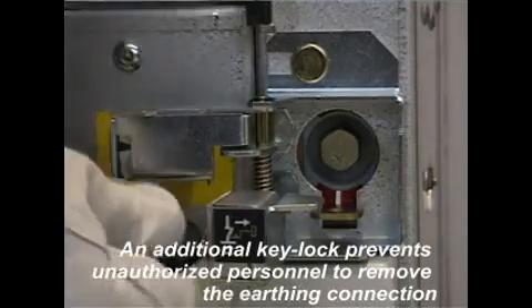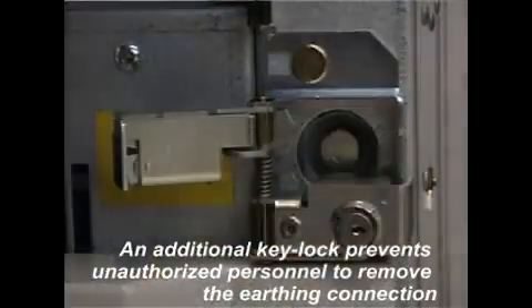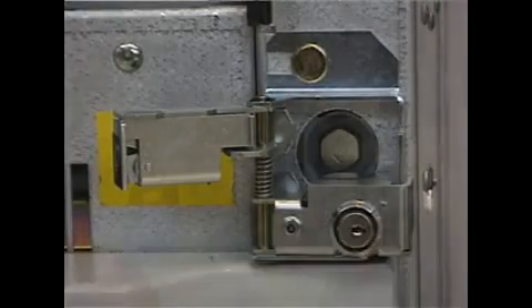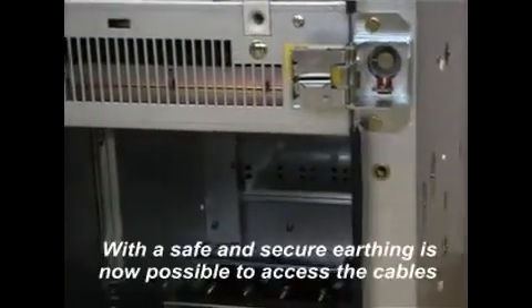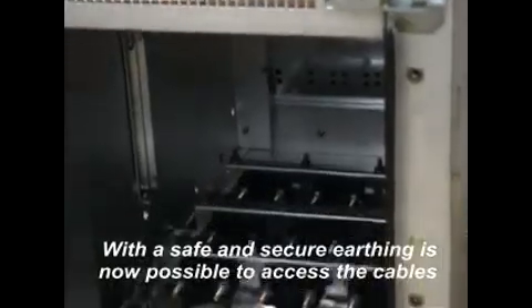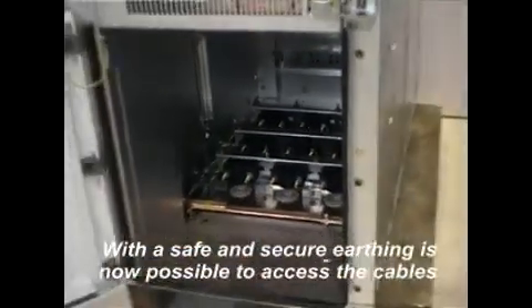Now that the earthing switch is closed to ground, we can operate the key lock and remove the key to make sure nobody will operate it while we work on the cables. When the earthing switch is closed, we can open the cable compartment door to get access to the cables.